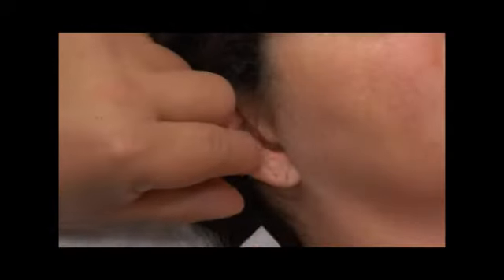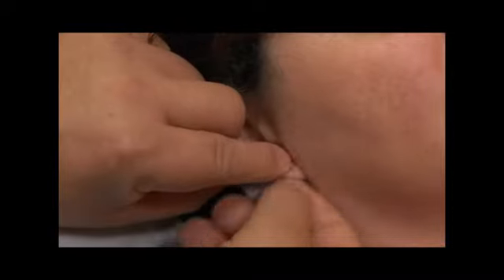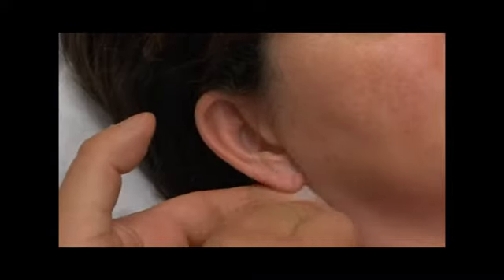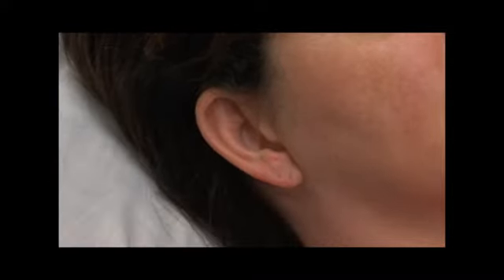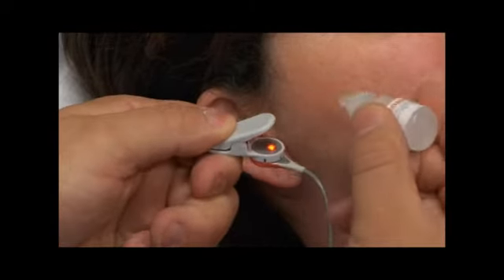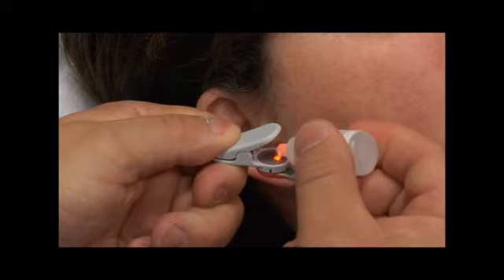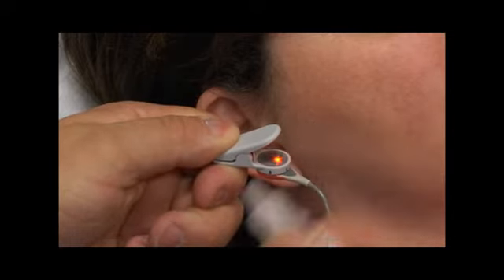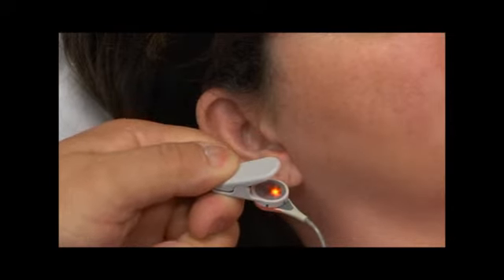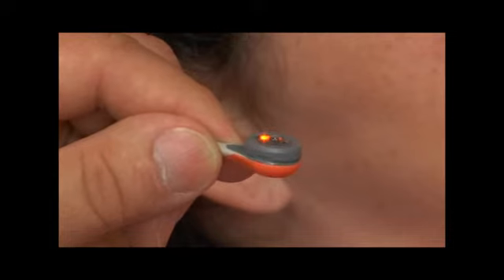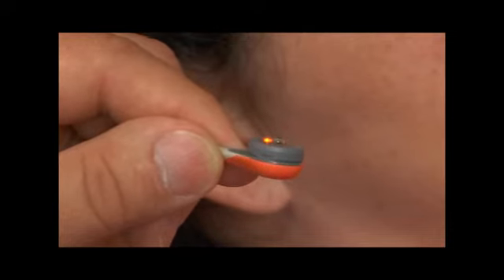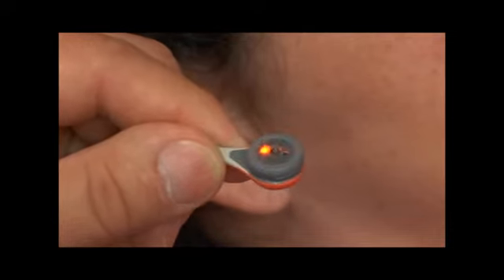Reattachment to the patient. Ear clip. Clean the earlobe with a swab wetted with 70% isopropyl or according to procedures applying to your institution and let it dry. Place 1 small drop of Sentec contact gel or water to the sensor membrane. Please note that Sentec contact gel works better for applications where the sensor is attached in a vertical fashion, as it is more viscous and water may slide off.